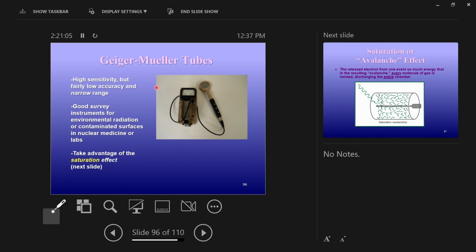So noble gases work great inside of Geiger-Müller tubes. The noble gas called argon, you'll see it the third one down on the right, Ar, that's argon. And argon's full. It can't take anything in its outermost shell, and so it's easily ionizable. In most of these tubes there will be a noble gas, but specifically in Geiger tubes, it's argon gas. Neon signs use noble gases because they emit pretty colors of light, and in Geiger tubes, noble gases work great because they're already full and they can ionize very easily. So that's part of what makes them very sensitive.